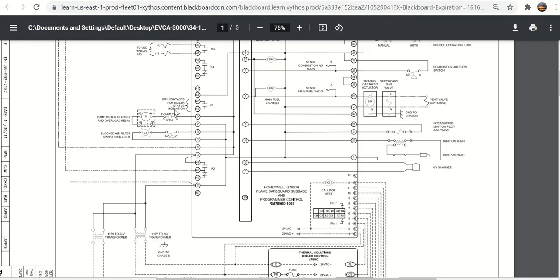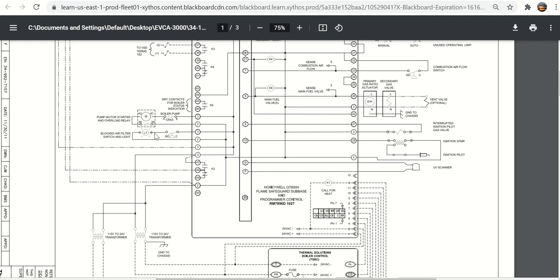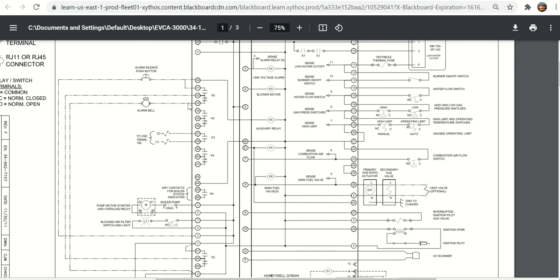Getting back to the diagram. Here you see this would be power coming out to the pump motor starter. Here is the blocked air filter switch and light. Here's the switch, pressure switch. Here's the actual light. Anytime you see this blocked air filter light on, that means that automotive style filter that filters the air going into the blower needs to be cleaned or replaced. You would first pull the foam element off and wash it. It's a washable foam element. Then you would either blow out the pleated air filter with nitrogen or compressed air, or put a new element in there. Thermal Solutions would prefer you buy a new one from them every year.